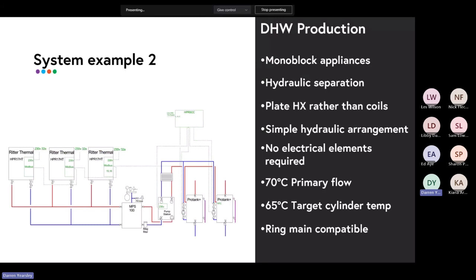And then in the storage tanks, all we have is a recovery pump, which moves the water from the bottom of the cylinder through the plate heat exchanger and then delivers it back into the top of the tank. So the tanks themselves are hydraulically separated. You have a separate cold in and hot out, and then we've got dedicated recovery ports on the side, so we can circulate the water through the plate heat exchanger independent of draw off. That gives you the most consistent delivery temperature out of these tanks, where you can arrange it that way. Sometimes we've got a bank of infinities. I see they use the bottom connection of the tank for the recovery to the infinities.